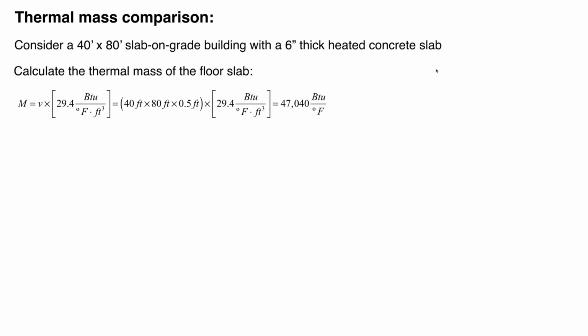We'll just use that as a starting point. The heating capacity or heat capacity of concrete, the number of BTUs it takes to raise a cubic foot of concrete 1 degree Fahrenheit, is 29.4. So we just multiply that by the volume of that slab, and you can see we come up with a thermal mass of roughly 47,000 BTUs per degree Fahrenheit.